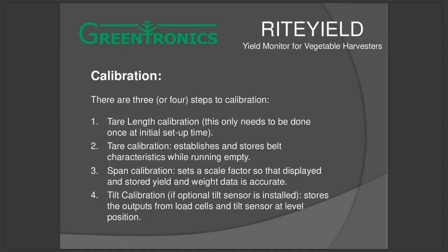I want to talk a little more about the Tare calibration procedure. This gets us the most questions on our tech support line. Before you start a Tare calibration, make sure the belt is actually empty. That's easy to figure out. Keep it running, go to the Tare calibration menu on the console, press enter, let it run as mentioned before, and when it reaches the end, save it.